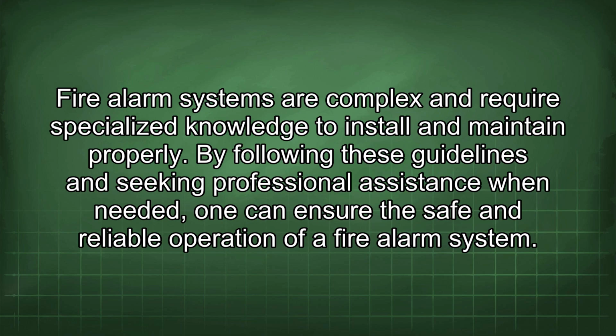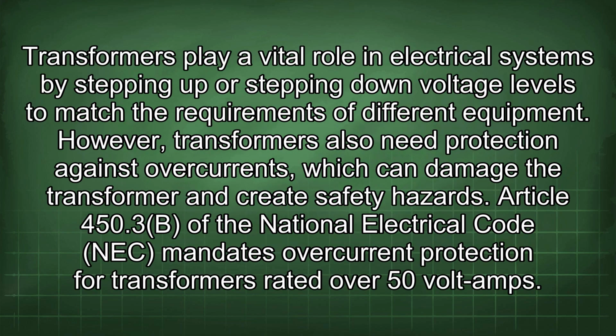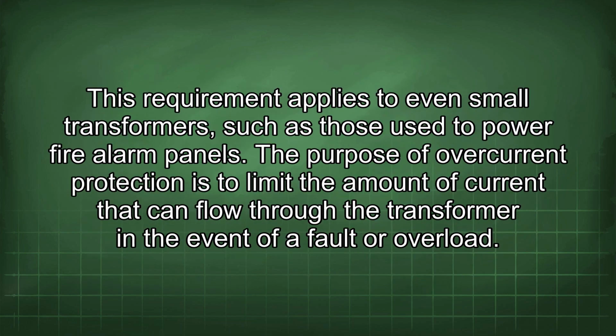fire alarm system. Transformers play a vital role in electrical systems by stepping up or stepping down voltage levels to match the requirements of different equipment. However, transformers also need protection against overcurrents, which can damage the transformer and create safety hazards. Article 450.3(B) of the National Electrical Code (NEC) mandates overcurrent protection for transformers rated over 50 volt-amperes. This requirement applies to even small transformers, such as those used to power fire alarm panels.